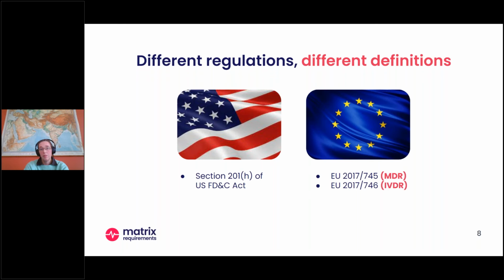One example is veterinary products. Veterinary products are within scope of medical devices in the US. It's part of the definition, while it's excluded from the definition of medical devices in Europe. In Europe, the definition of a medical device only focuses on products for human use, and so all veterinary products are excluded. There used to be a directive in Europe on veterinary products, but that was repealed in 2008 and has never been replaced. So at this moment, medical devices for veterinary use only are considered to be consumer goods. That's one very clear example of the differences, but there are more subtle differences as well.